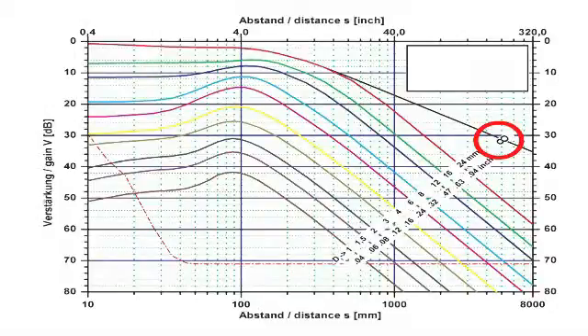Additionally, the noise level is also shown on the DGS diagram. This noise level tells the user the difference in dB between the echo amplitude of a given ERS, and the noise level at this specific depth.